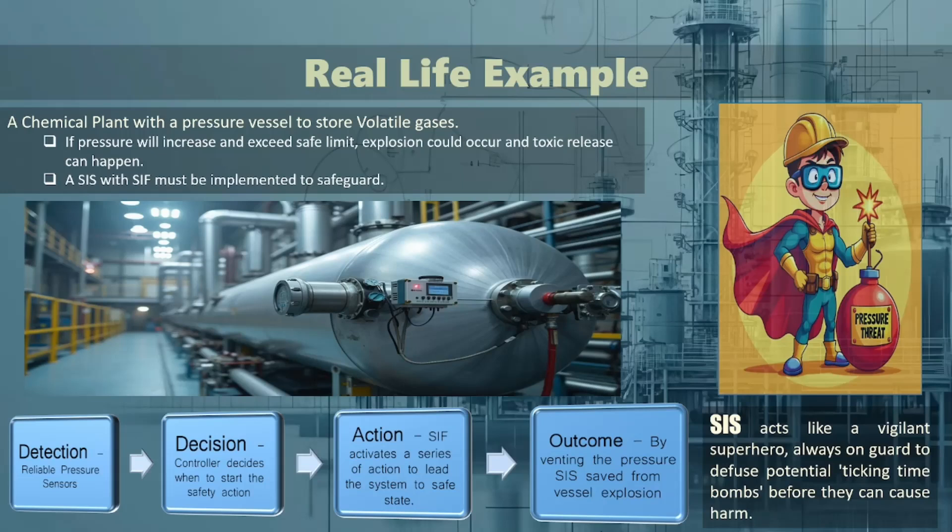Here's how it works. Detection: the system includes pressure sensors that continuously monitor the vessel's internal pressure. These sensors are highly reliable and calibrated to detect even slight deviations from normal pressure levels. Decision: when the pressure approaches a critical threshold, the logic solver within the SIS evaluates the data and determines whether the situation requires intervention based on preset safety parameters. Action: if the pressure is deemed too high, the SIF activates a series of actions, which might include opening a relief valve to safely vent excess pressure into a flare system or a containment area, thereby reducing the pressure within the vessel.